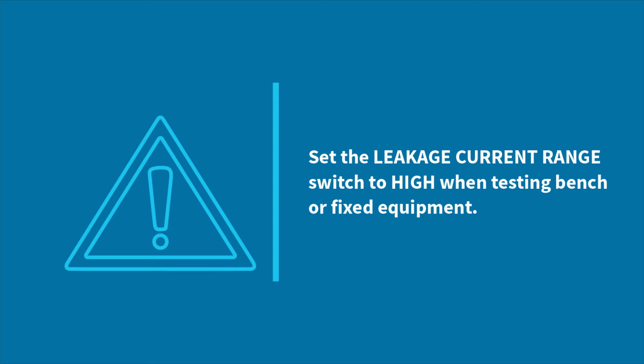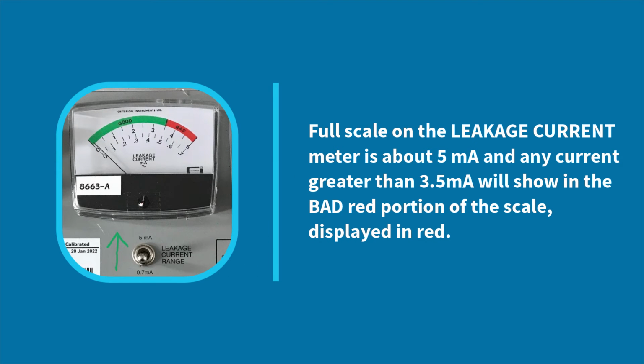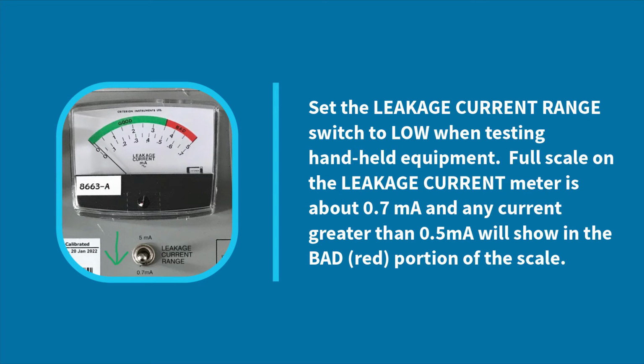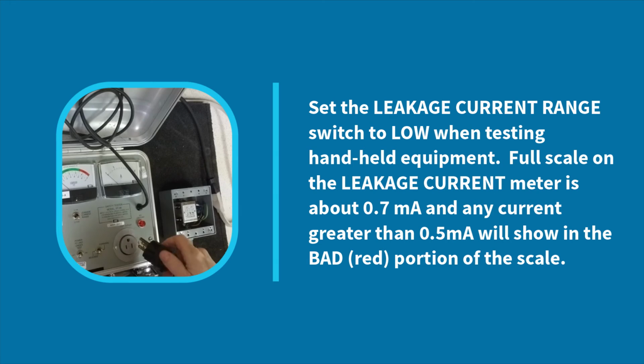Set the leakage current range switch to high when testing bench or fixed equipment. Full scale on the leakage current meter is about 5 milliamps, and any current greater than 3.5 milliamps will be displayed in the bad red portion of the scale. Set the leakage current range switch to low when testing handheld equipment. Full scale on the leakage current meter is about 0.7 milliamps, and any current greater than 0.5 milliamps will show in the bad red portion of the scale.